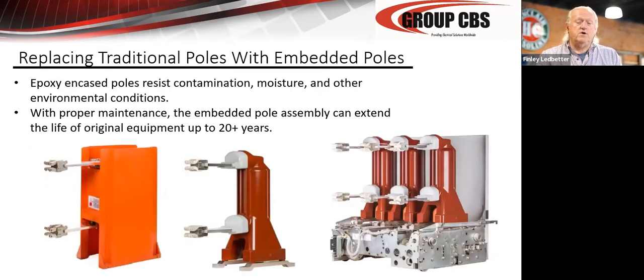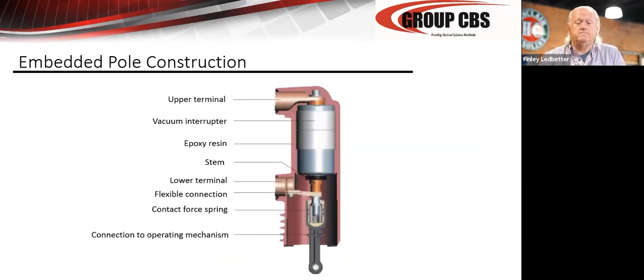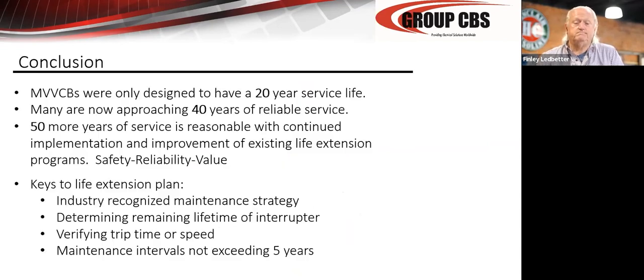As you see here, there are replacement poles. On the left is an assembled pole, and the center is a replacement embedded pole. And you can see this GE breaker has had the embedded poles placed on it. So if you go to buy new poles for your breaker, if you can get rid of the assembled poles, the epoxy embedded poles are a better way to go. The embedded pole essentially has the same vacuum interrupter in it. It's the same structure. It's just cast in a block of epoxy, which does a lot of good things for you.